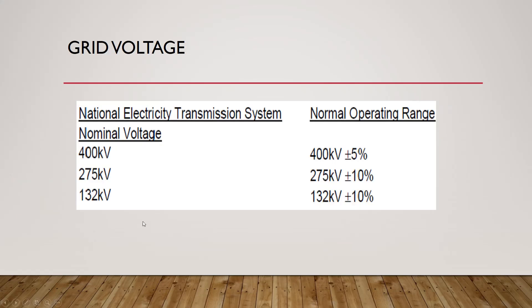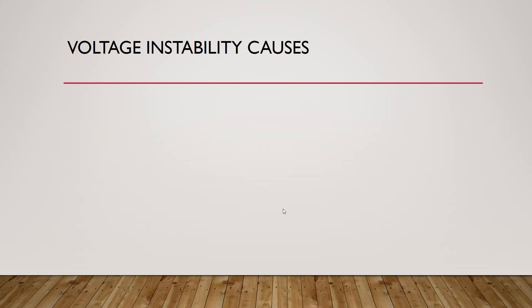As an example of voltage tolerance ranges: for a 400 kV grid voltage, we can vary it by plus or minus 5%; for 275 kV, it is plus or minus 10%; and for 132 kV, it is also plus or minus 10%. These are the allowable ranges within which we can change our voltage.